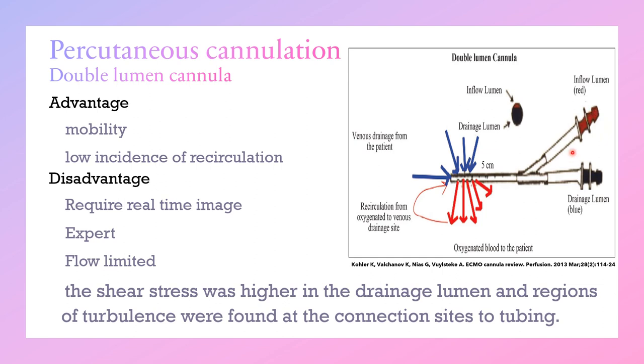As a double-lumen cannula has two lumens — an inflow lumen and a drainage lumen — they open into a single lumen which is divided into two parts; the drainage lumen is twice the size of the inflow lumen. The advantages of the double-lumen cannula include easy patient mobility, single-site insertion, and a low incidence of recirculation. The disadvantages include the requirement for real-time imaging, the need for an expert team for insertion, flow limitation in patients with high body mass index, higher shear stress in the drainage lumen, and regions of turbulence at the connection site to the tubes.